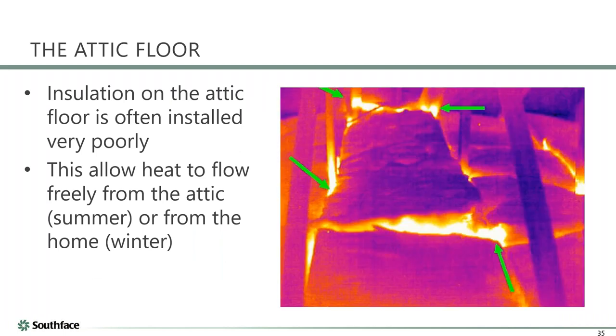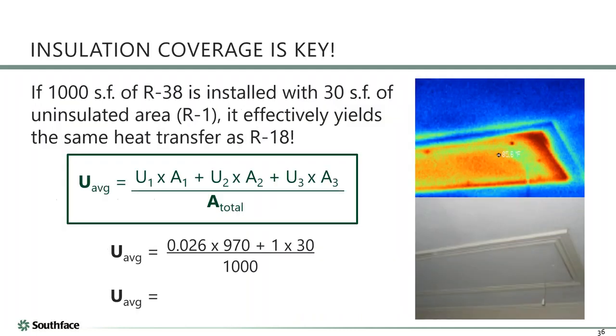Another reason for performance improvement is coverage consistency. In a 1,000 sq ft attic, even 3% of the insulation area at R-1 — say the attic hatch plus a few can lights — gives the same heat transfer as R-18. So an R-20 spray foam roof line with 100% complete coverage would actually perform better than R-38 insulation that is deficient at just 3% of the area. Heat takes the path of least resistance.